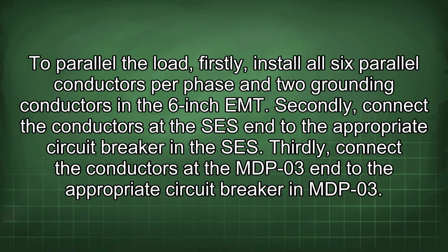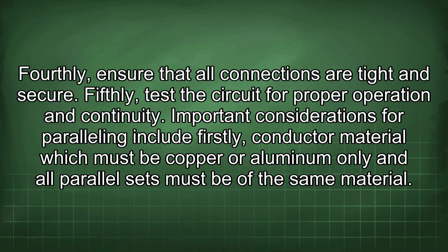To parallel the load, firstly, install all 6 parallel conductors per phase and 2 grounding conductors in the 6-inch EMT. Secondly, connect the conductors at the SES end to the appropriate circuit breaker in the SES. Thirdly, connect the conductors at the MDP-3 end to the appropriate circuit breaker in MDP-3. Fourthly, ensure that all connections are tight and secure. Fifthly, test the circuit for proper operation and continuity.